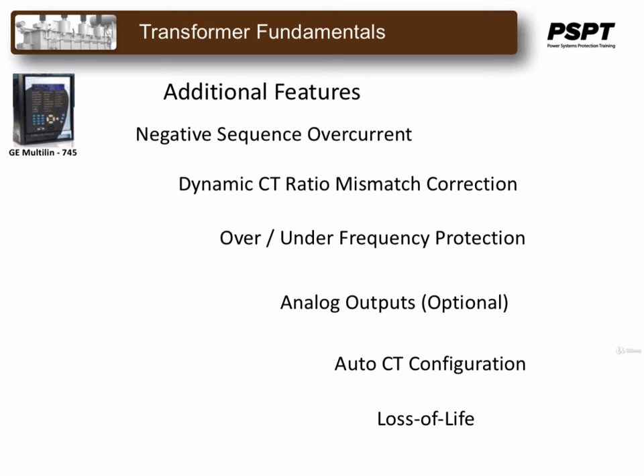The loss of life feature provides an estimate of how much the transformer's total insulation life has elapsed based on IEEE standards guide for loading mineral oil immersed transformers and guide for loading dry type distribution and power transformers.